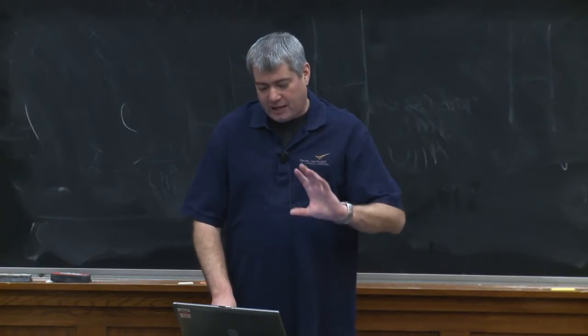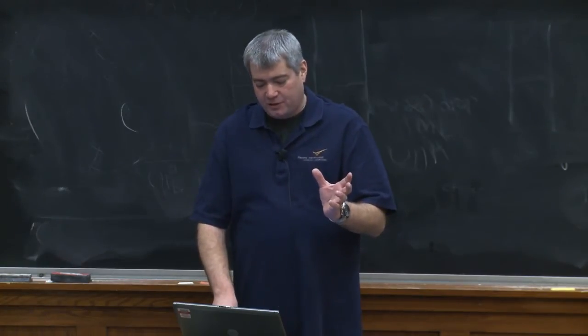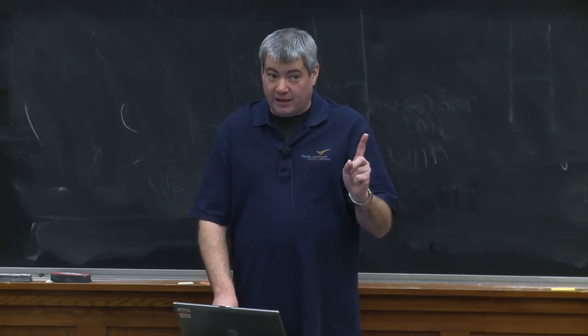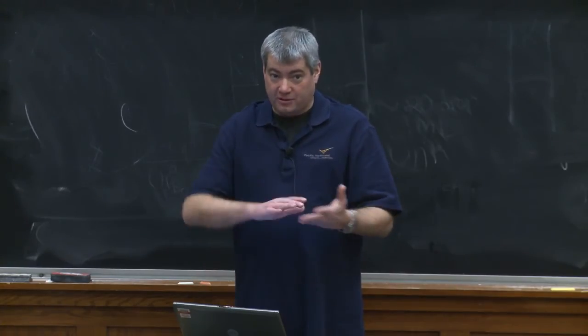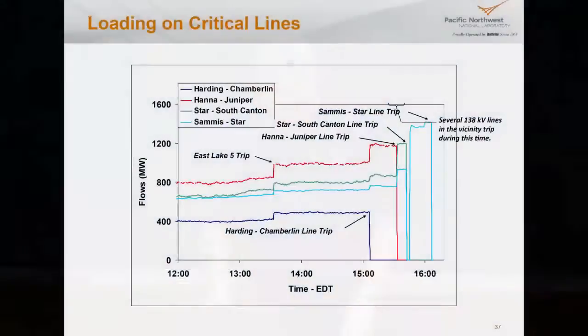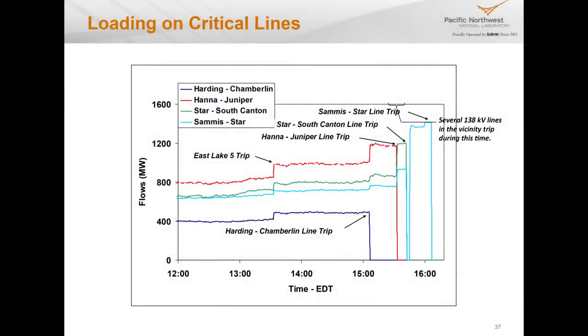And at this point in time, the sequence of events shifts, because once you lose one line that way, you're going to lose other lines that way. It's a domino effect at that point. And this shows all the way back from noon getting up to that point. What this plot shows is the flow on all of these lines I'm talking about. And you can see right here, shortly after 1 o'clock, that's the effect of that power plant that tripped I talked about. So the power plant tripped, so more flow through the lines to make up for it.